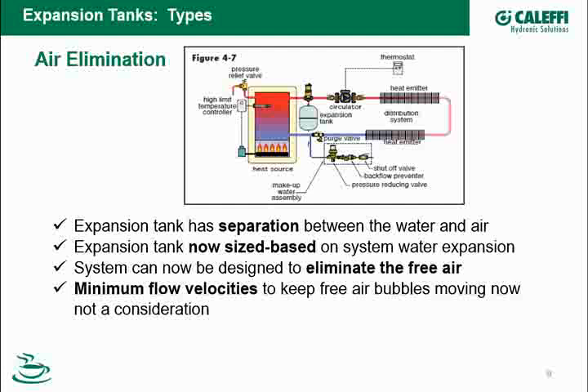Under 12 psi, if my cold static pressure in the system is around 12 psi, typically a pre-charged tank is about half the size of a plain steel tank. Now, by having that separation, it's going to eliminate the air moving from the air side into the water side, so I now can design an air-free system or an air elimination system.